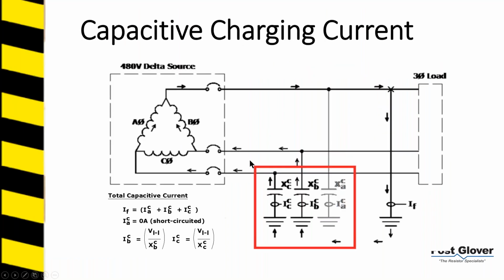That's why it's called that. So you have it here. This designates your capacitive charging current. You essentially have a faulted phase, and you have a vector sum of your currents here, and that's your system's capacitive current. Like I mentioned before, if you had an ungrounded circuit and you had an intermittent fault, you could potentially charge this and get overvoltages. So when we have a resistor, we need to make sure that the current level for the ground fault is higher than this level. That's the idea.